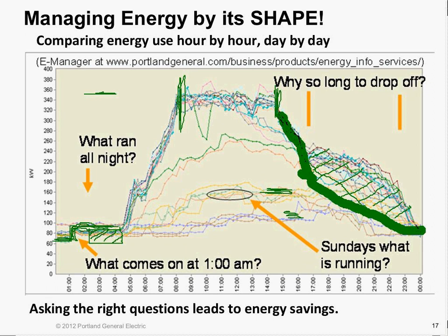The last question they never got an answer on is why were Sundays running higher than Saturdays? I think they finally figured out that we're renting out some space to a church group. There were some things going on. So sometimes you may be confused by a number, and the chart simply gets you at knowledge that you didn't have before about what's going on in a particular building.